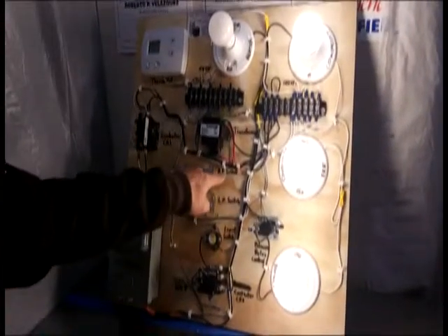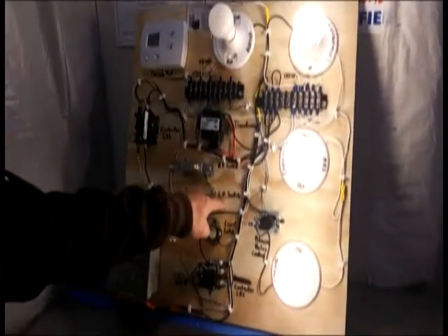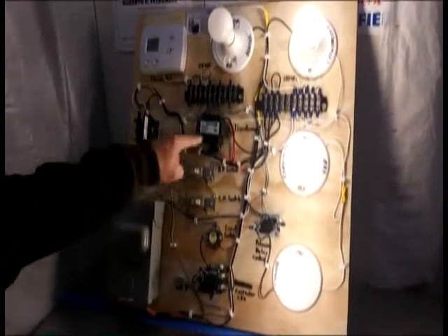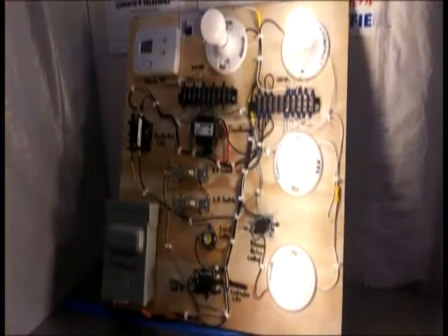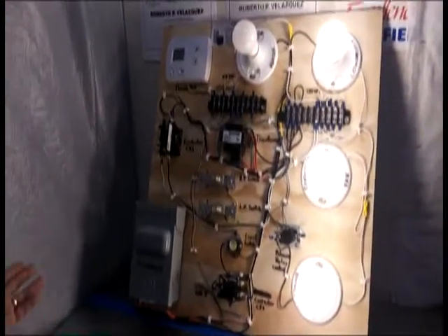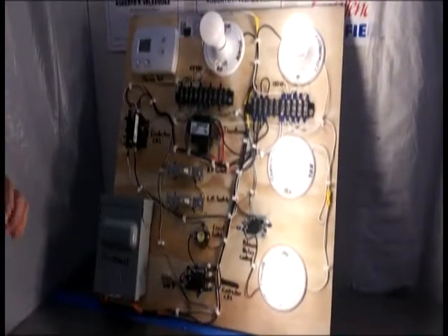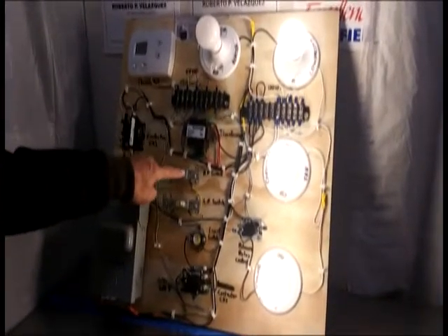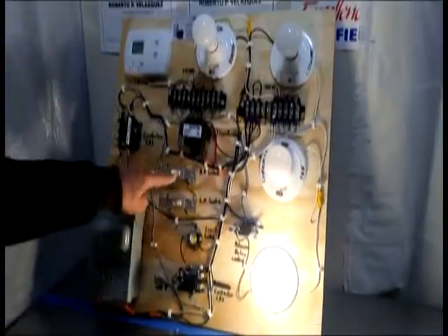So now, see, we have two switches right here. We have the high pressure switch and the low pressure switch. Those two switches protect the compressor. Let's see, for instance, if the condenser coil is dirty or something like that, it's going to increase the high pressure. And when the high pressure increases, this switch is going to open. Okay? You can see it.